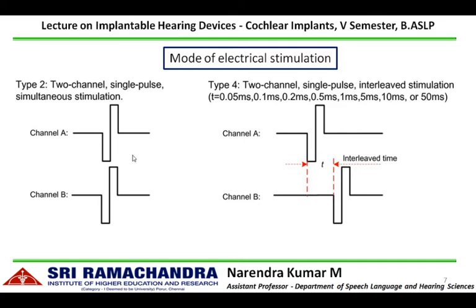Pulsatile stimulation can be delivered in two modes: simultaneous stimulation or non-simultaneous stimulation. In simultaneous stimulation, all electrode contact areas fire or get activated at the same time. In non-simultaneous stimulation, at any given point in time no two channels or electrode contact areas are active simultaneously — this is called non-simultaneous or interleaved stimulation.